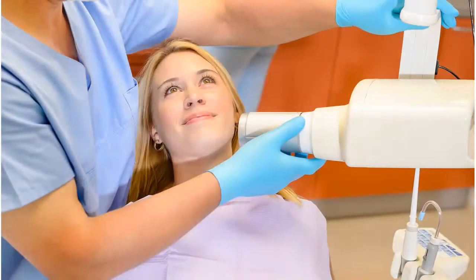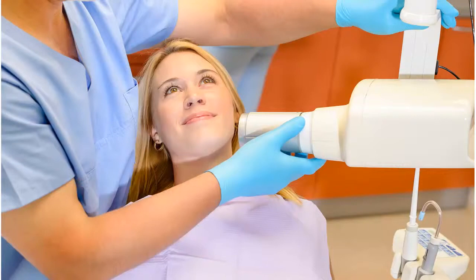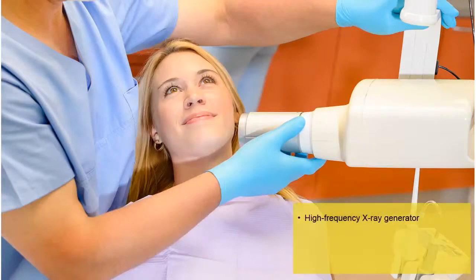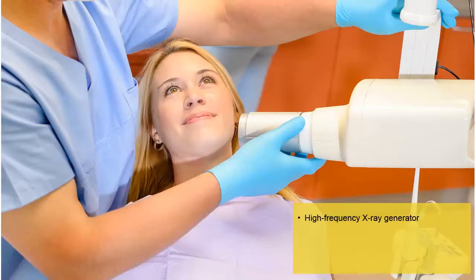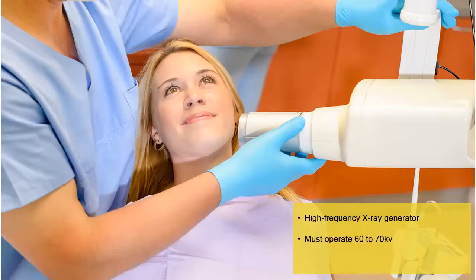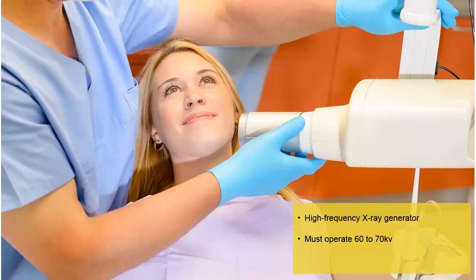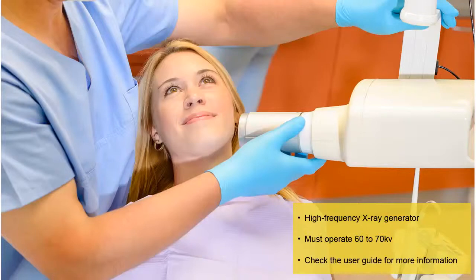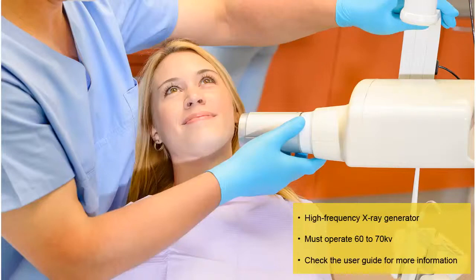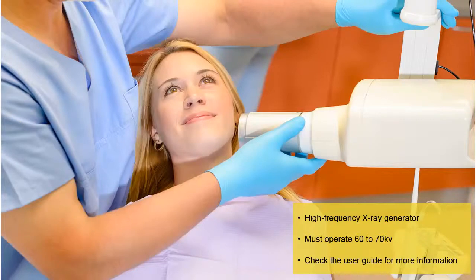The RVG sensor is compatible with all X-ray generators that meet the current standards of intraoral radiology. We recommend a high-frequency X-ray generator so that the patient is exposed to a lower dose of radiation. The X-ray generator must operate with a voltage of 60 to 70 kV. The RVG sensor is not compatible with generators that have a voltage less than 60 kV. The user guide provides a table of suggested exposure times for an X-ray generator output of 70 kV and 7 ma. These are suggested exposure times only, as exposure times vary by type and age of the generator.